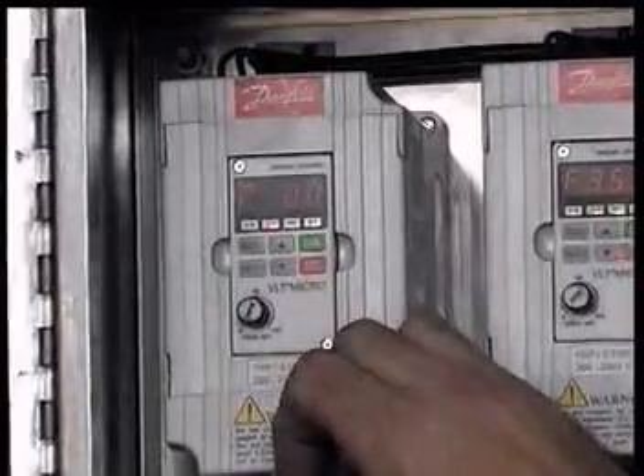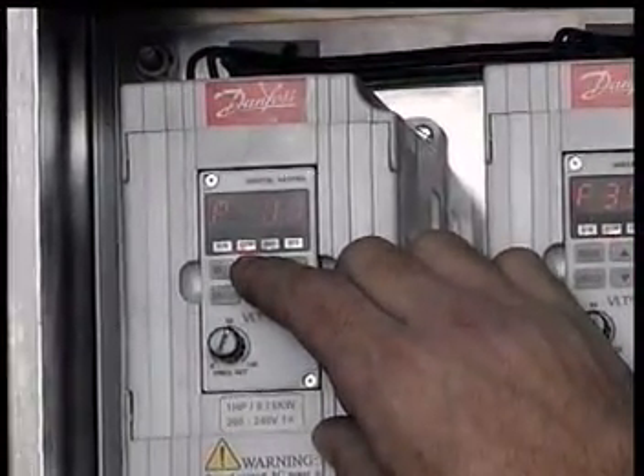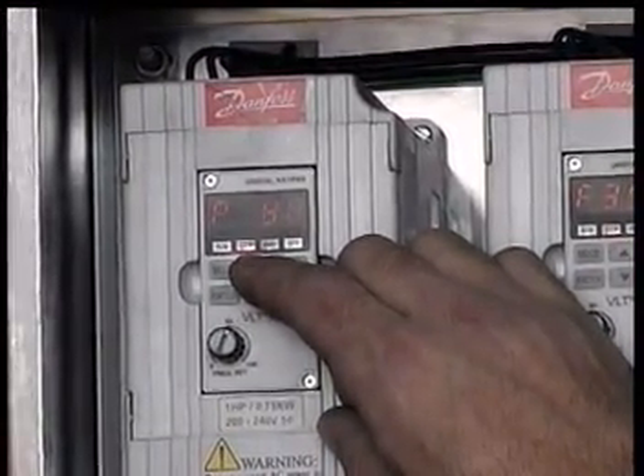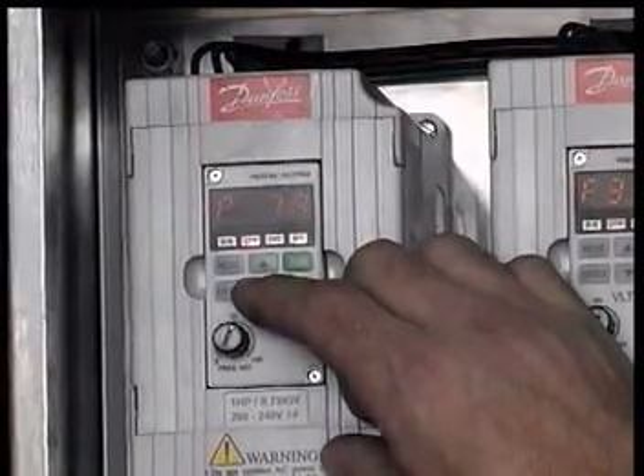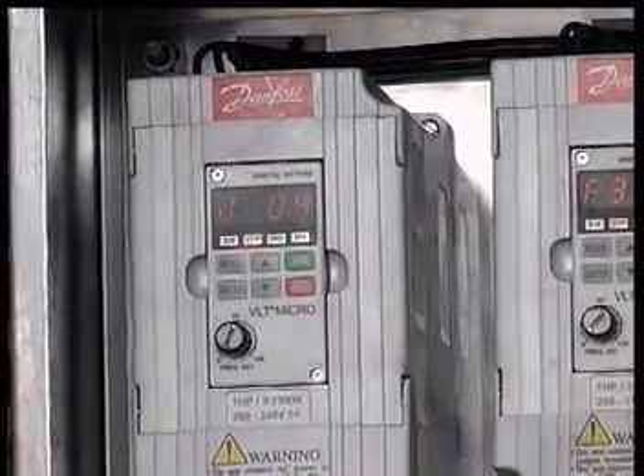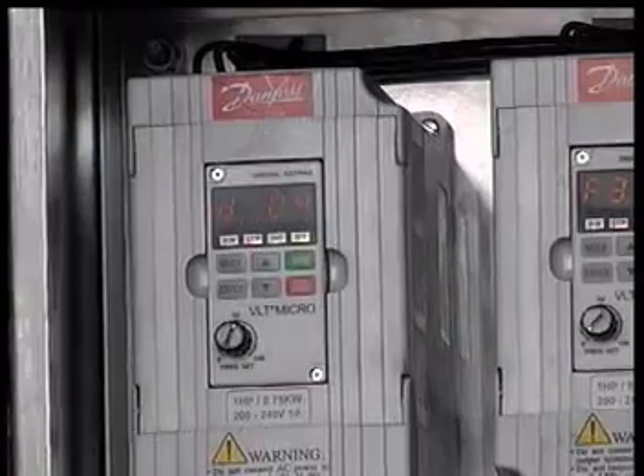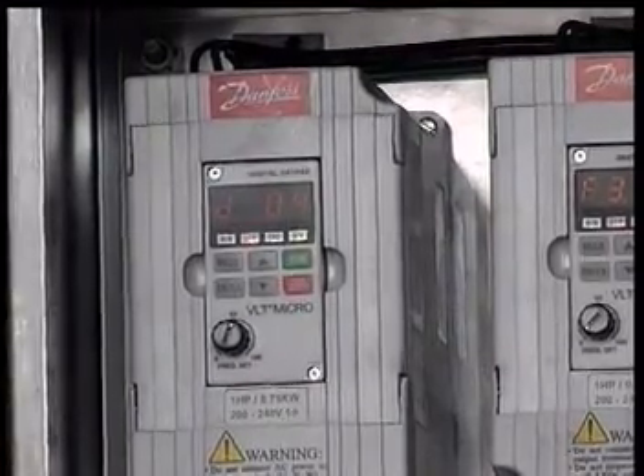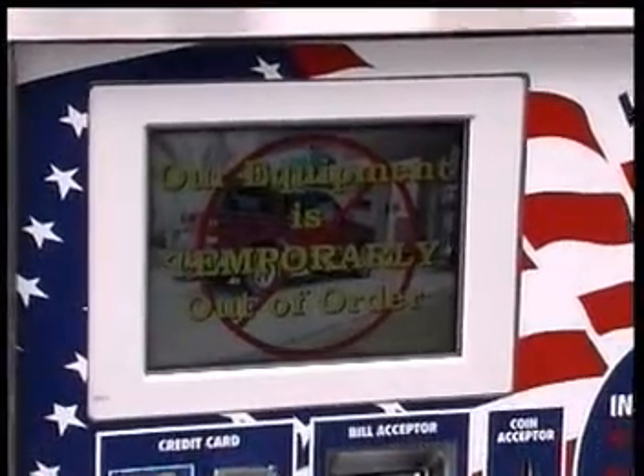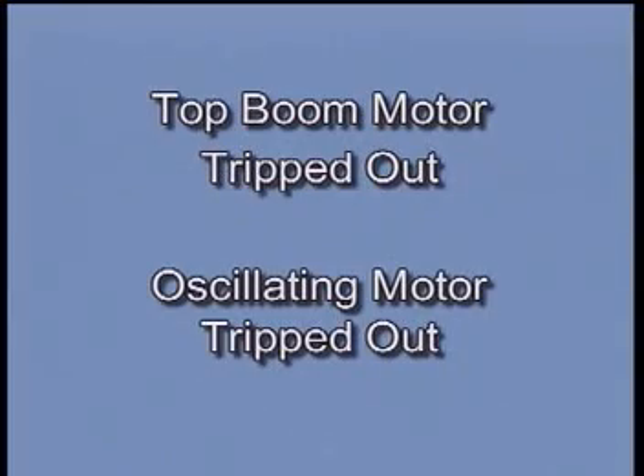Refer to the Danfoss Variable Speed Drive section of the Water Wizard Manual for operating instructions. Check P73, 74, and 75. These are the last 3 fault codes recorded. Note these, then refer to the Danfoss Manual for a list of fault code descriptions. Then follow the recommended steps for troubleshooting. This fault will also shut down the entrance controller. For these fault conditions, follow the same instructions as the drive motor section.